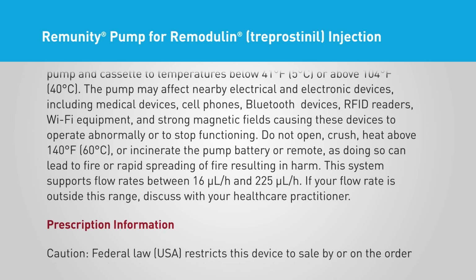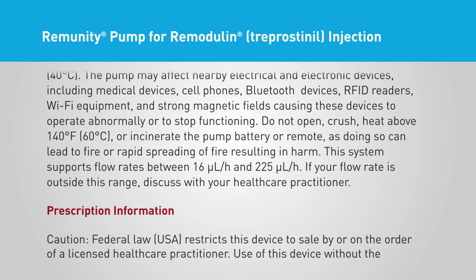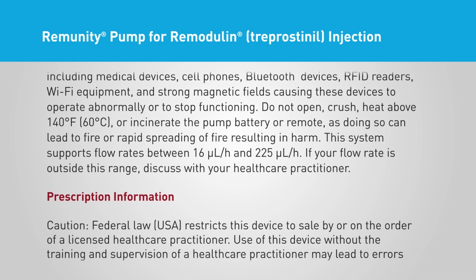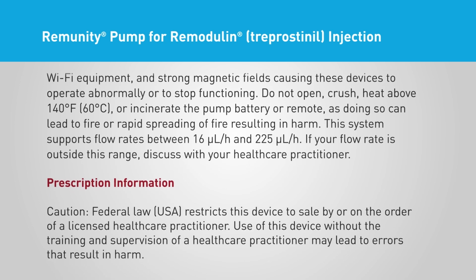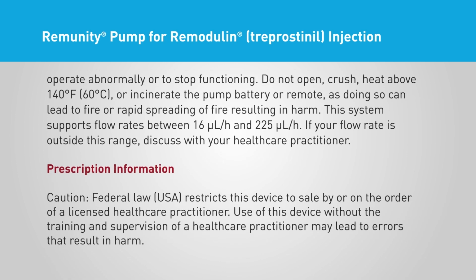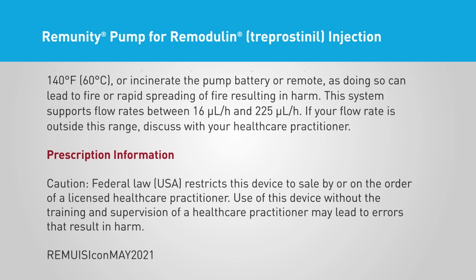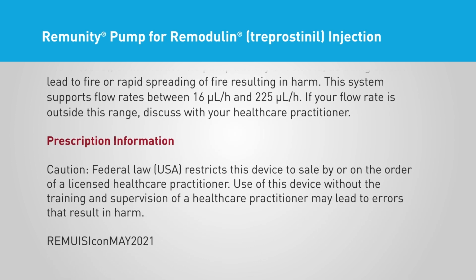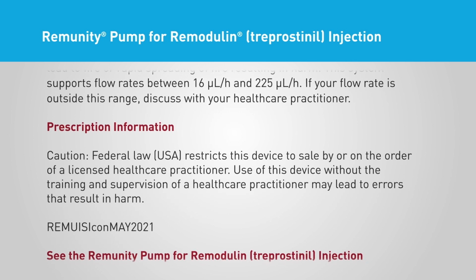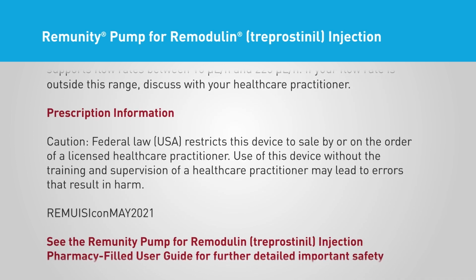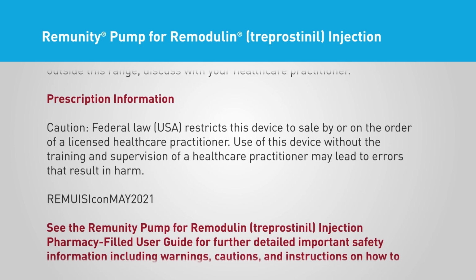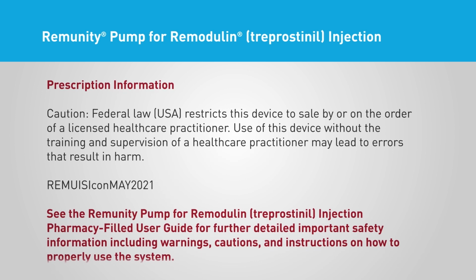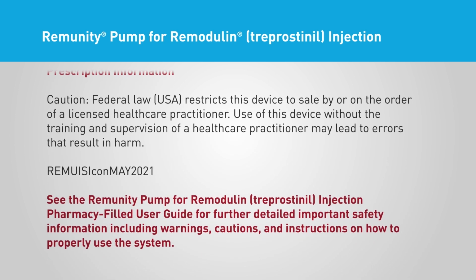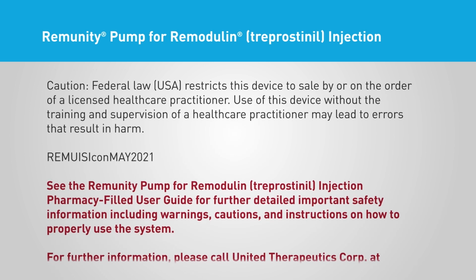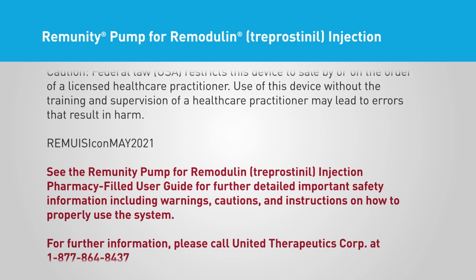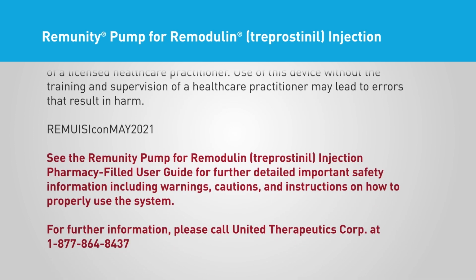Do not open, crush, heat above 140 degrees Fahrenheit, 60 degrees Celsius, or incinerate the pump battery or remote, as doing so can lead to fire or rapid spreading of fire resulting in harm. This system supports flow rates between 16 microliters per hour and 225 microliters per hour. If your flow rate is outside this range, discuss with your healthcare practitioner. Prescription information. Caution: federal law, USA, restricts this device to sale by or on the order of a licensed healthcare practitioner. Use of this device without the training and supervision of a healthcare practitioner may lead to errors that result in harm. See the Remunity Pump for Remodulin treprostinil injection pharmacy-filled user guide for further detailed important safety information including warnings, cautions, and instructions on how to properly use the system.